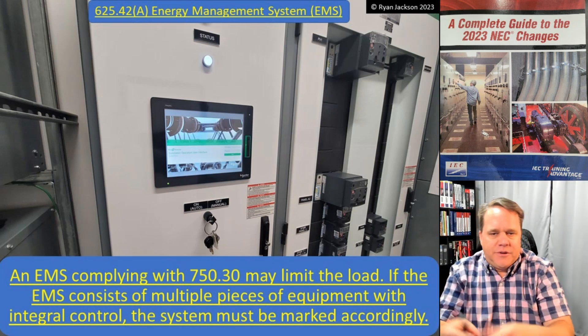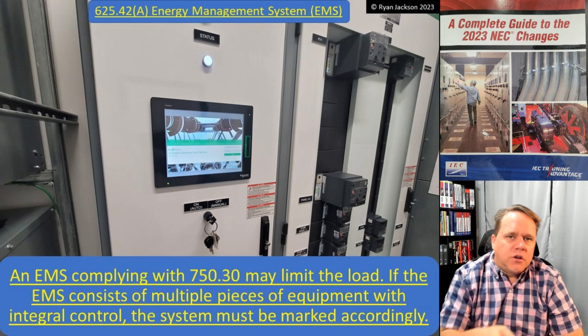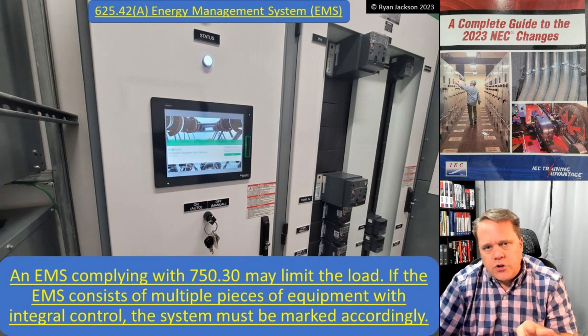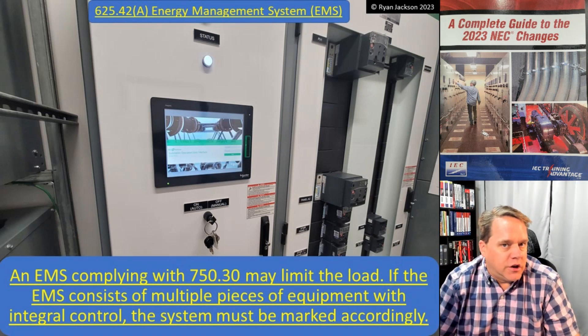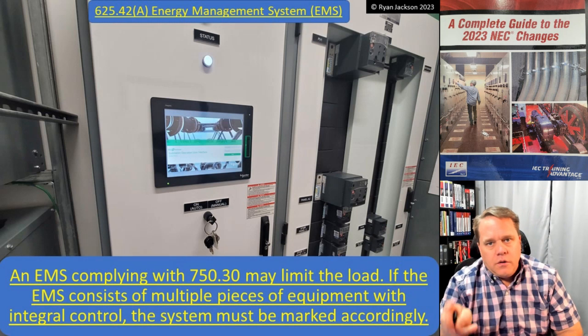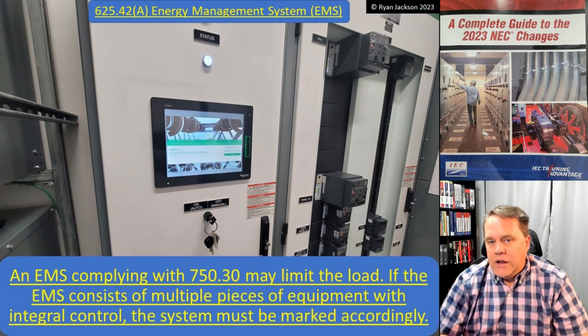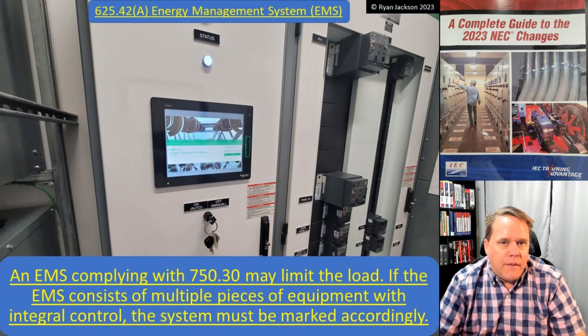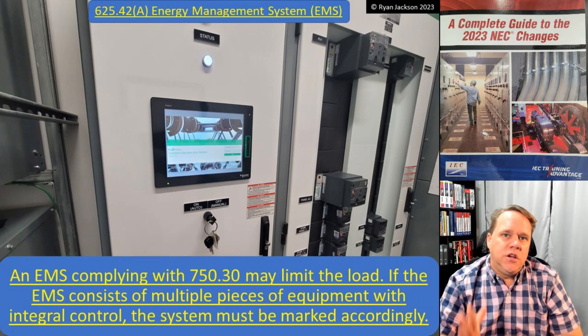You can program your energy management system to talk to the EVSE and determine how much current goes out based on total need. Say I put in five 30-amp EVSE units on one circuit — that doesn't satisfy the general rule, but with an EMS it's allowed. If one car plugs in, I give it 30 amps. Two cars, each gets 15 amps. Five cars, each gets 6 amps. It might take a while to charge at 6 amps, but if you leave it plugged in overnight you might be okay. We let the technology steer the ship.